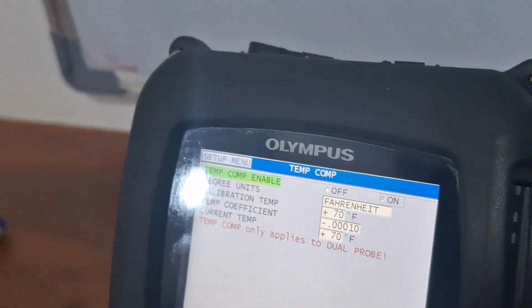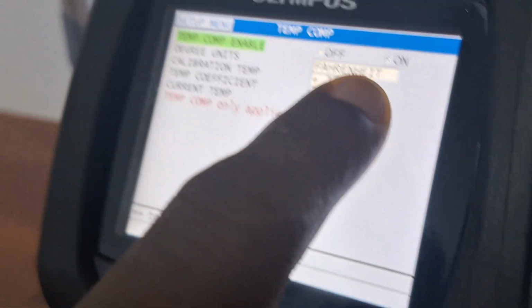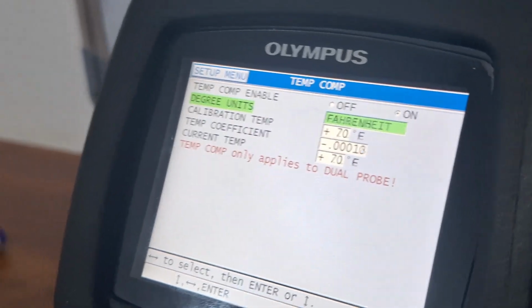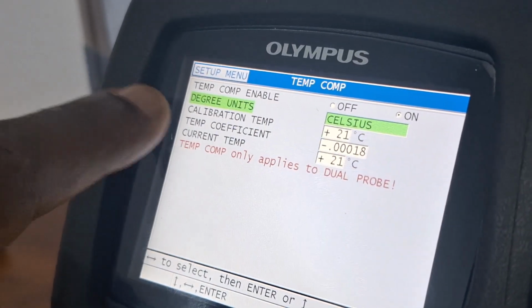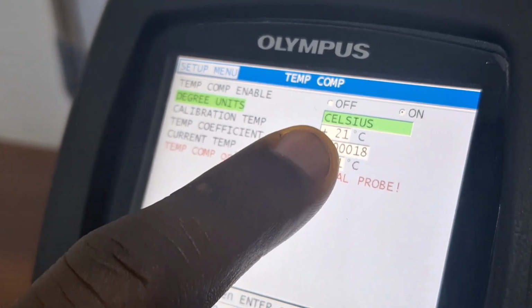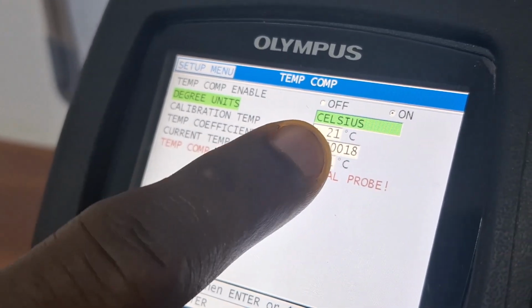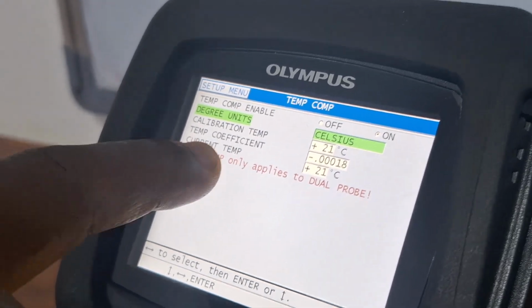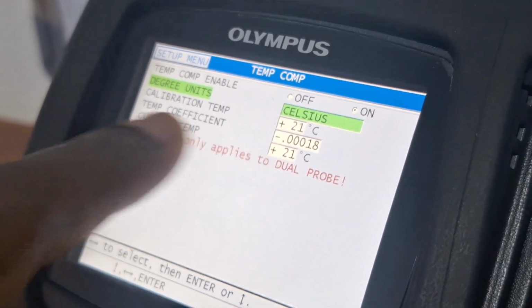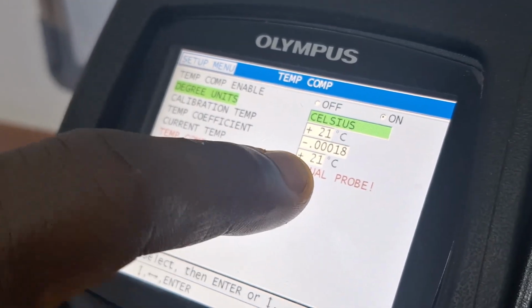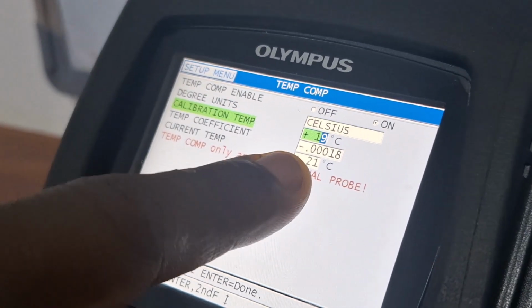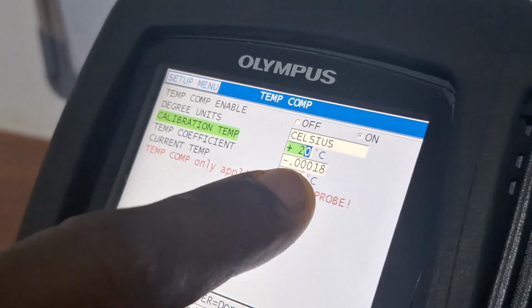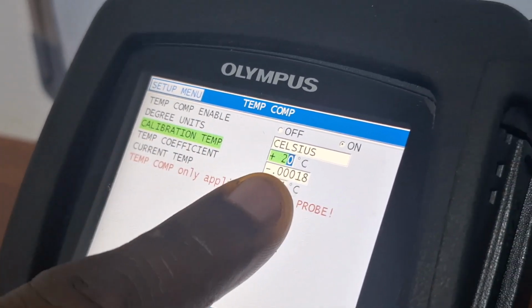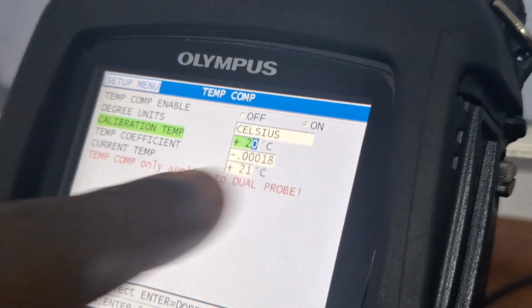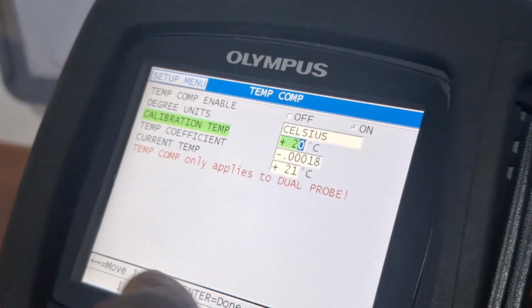When you have ensured that your high temperature probe is in use, your temperature is in Fahrenheit here. You can convert to degrees Celsius. Look at the option, so it's in Celsius. Now, your calibration temperature, this is the temperature of your calibration block, which is usually your room temperature. So you put that, and your current temperature, which is the temperature of the material you are going to measure. So if it's at 200 degrees Celsius, you come to this place and put your 200 degrees or whatever the temperature. Your temperature coefficient, you can calculate on your own or automatically. The machine does that for you.